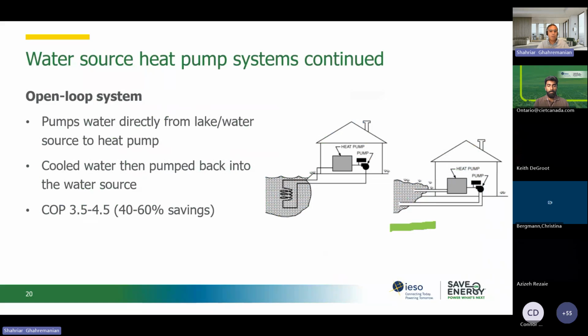In the open loop that you see here, we take the water directly to our heat pump, and then we dump it back, let's say in summer mode, we dump back the heated water to the lake and so on. This is also good, but there are some environmental considerations, which don't allow us to do it in many places. So we should check for this. But the COP of these water source heat pumps is good. It is higher than the air source heat pump, and their efficiency is also much better.